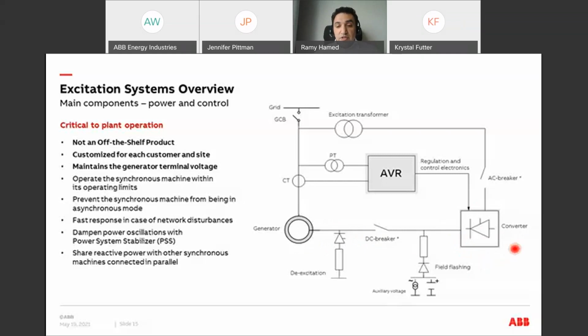Normally, this converter is a thyristor bridge. And the most common supply for the excitation system is from the generator terminal. And so we need the excitation transformer to step down the generator voltage and to provide galvanic isolation. However, the excitation transformer needs to be of specific design to support the converter operation and the thyristor commutation, and to provide as well the maximum current that the system needs. The excitation system needs to be designed as well to have an AC or DC breaker that can interrupt the flow of current to the rotor.